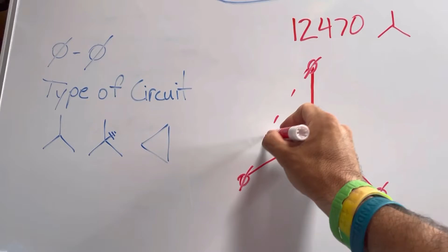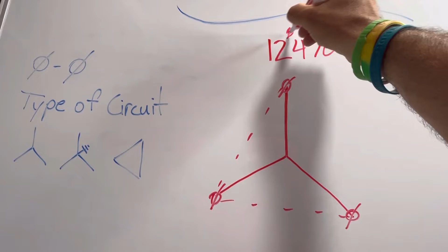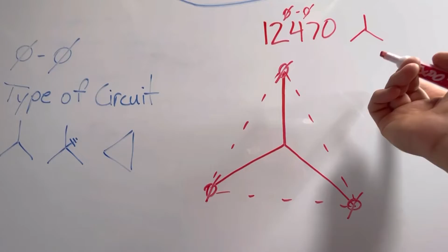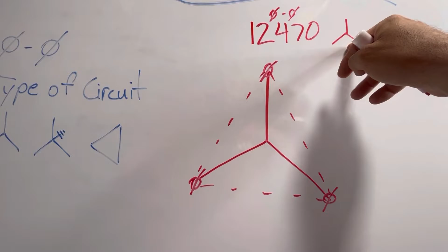So I've got phase, phase, and phase, right? So from phase to phase, my phase-to-phase potential is 12470, right? My phase to neutral potential on this circuit is 7200. But we don't say that. We don't even worry about saying that. The only thing that we say is the phase-to-phase potential and the type of circuit that it is. In a Y circuit, it's just assumed. You don't even have to say it. It's just assumed that the phase to neutral voltage is 7200 volts. You just don't have to do it.